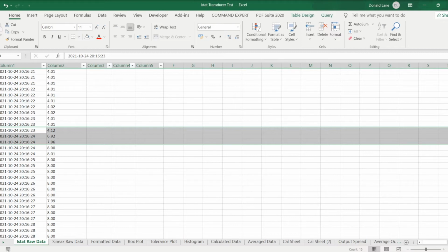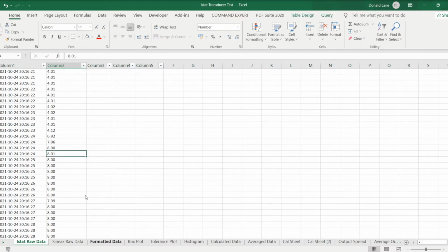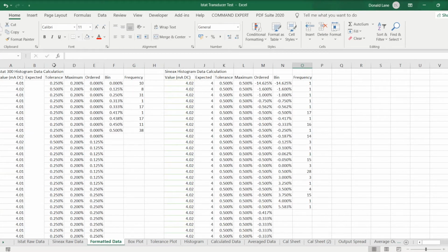The Fluke is also recording around about 4 readings per second, so it isn't fast enough to measure the response time of the transducer. To do that I'd have to use an oscilloscope or something like that. So that's the first little issue that I have with regard to this. Once I've removed all these slightly erroneous readings here, I can then move on to formatting the data and calculating the tolerance, the maximum, and then I calculate the data for a histogram, and that enables me to look at the other data that's available to produce some plots.